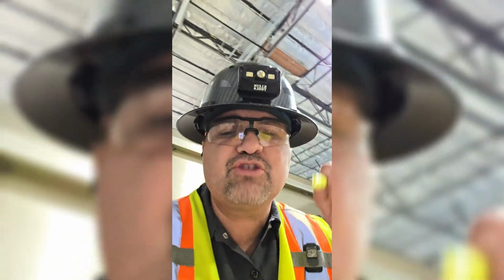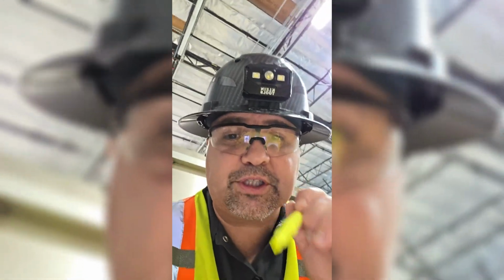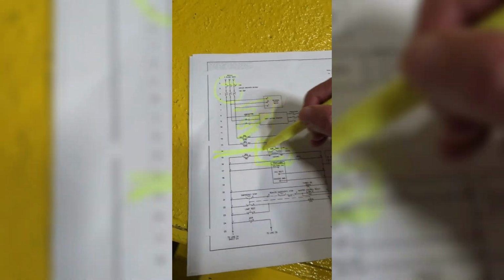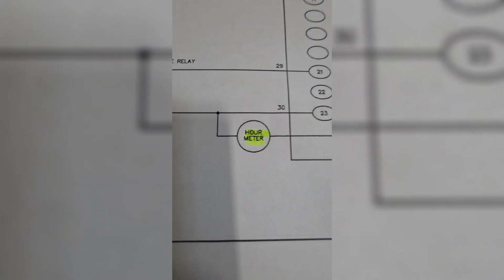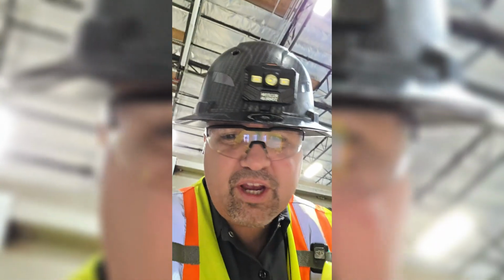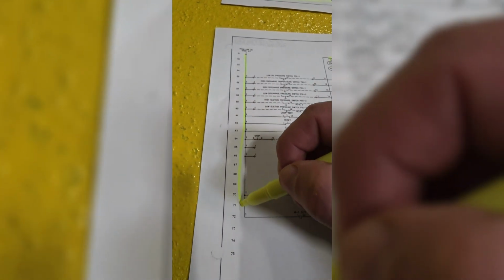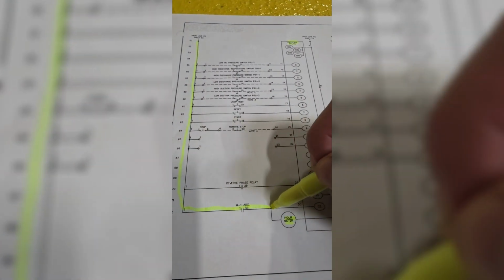This particular hours counter is running off the low voltage, not the high voltage. So this whole part of the circuit is not of interest to me. I want to see what's going on in this part. If you could read two words, hours meter, you'd be able to find this part on a drawing anytime. And that's really all you have to look for. This portion of the drawing is our PLC input card. And if you follow the line diagram all the way down, it leads you right to your hours meter.